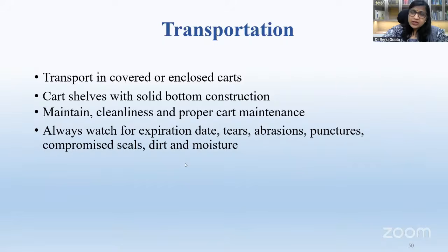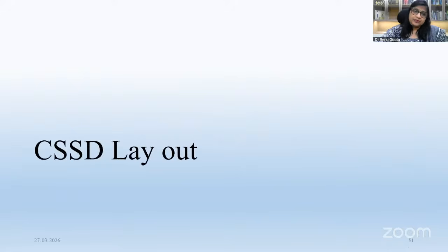So transportation is also important. You cannot use the same carts which were used to transport the dirty things into the CSSD. Either these carts are disinfected by passing through ultraviolet radiation or thermal disinfection, or you use separate carts for transporting the sterile supplies.